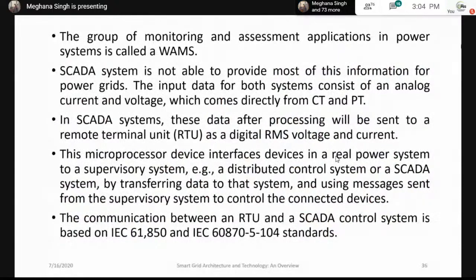A group of monitoring and assessment applications in power systems is called WAMS, wide area monitoring system. I would like to speak on SCADA. SCADA is not able to provide most of the information for power grids. It's an old system. The input data for both systems consists of analog current and voltage, which directly come from CT and PT. So I sense the current from CT and the voltage from PT. In SCADA systems, this data after processing is sent to RTUs, that is remote terminal units, and the data will be either digital RMS voltage or digital RMS current.